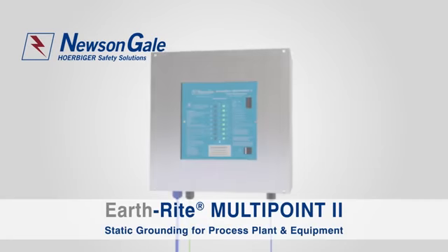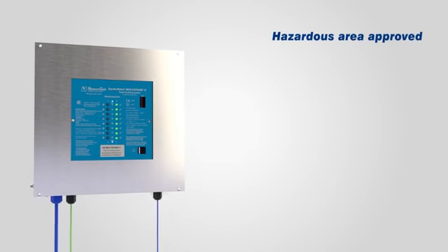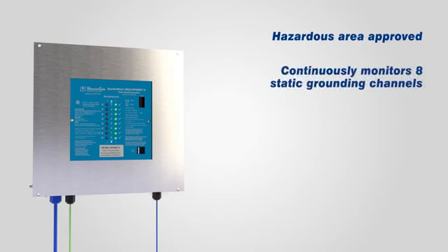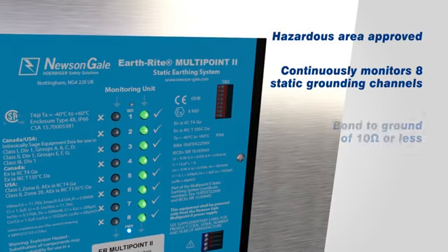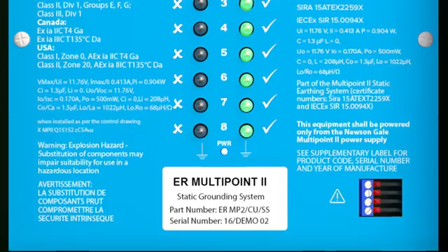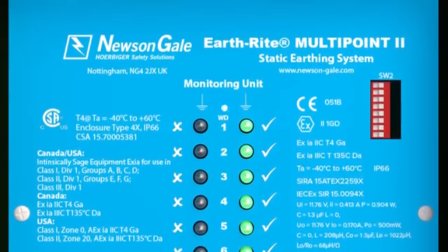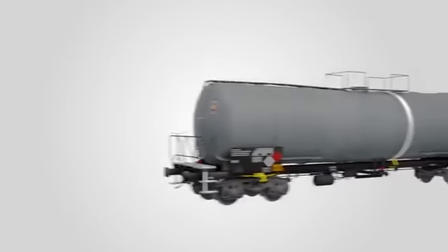The Earthrite MultiPoint 2 is Newson Gale's latest solution to multi-channel static ground monitoring for the hazardous area industries. Each unit is fully certified and capable of continuously monitoring up to eight independent static grounding channels, ensuring each connection achieves a low resistance bond to ground of 10 ohms or less, demonstrating compliance with the best practice approach stated in IEC, CENELEC and NFPA guidelines. The design improves upon its predecessor to incorporate a higher degree of safety and increased application flexibility, while providing reliable ground monitoring for a multitude of different processes.